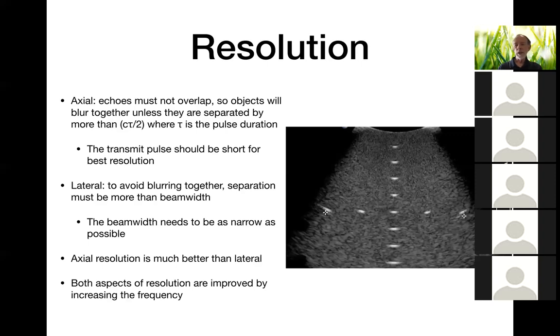You'll also notice, if you look at the points where a measurement has been made, where the little X markers are, that the lines out there are bigger. So right near the edges of the ultrasound image, the resolution is actually worse, the lateral resolution. And that's not uncommon. So a lesson from that is, when you want to see structures clearly and perhaps make measurements, make sure they're not right out in the fringes of your image. Make sure that they're in the central 2/3 or 3/4 of the image.